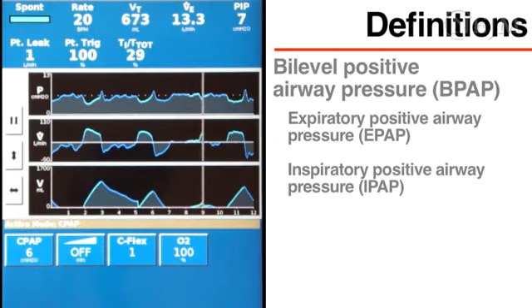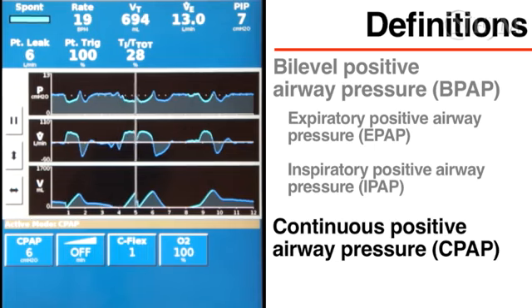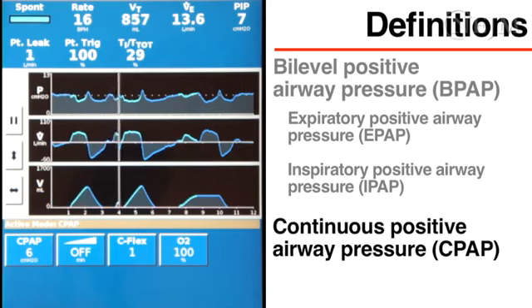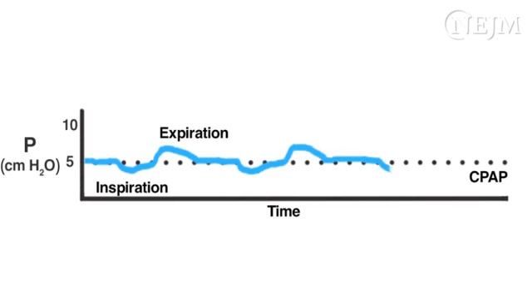Another common non-invasive mode is continuous positive airway pressure, or CPAP. CPAP is a spontaneous breathing mode that is distinct from BPAP. In CPAP, the ventilator delivers one pre-specified positive pressure throughout the respiratory cycle. It does not deliver additional inspiratory pressure, and therefore does not directly support ventilation. This graph shows airway pressure in a patient receiving CPAP. The pressure falls during inspiration as the patient takes spontaneous, unsupported breaths, and returns to the CPAP value during expiration. Many ventilators can also briefly reduce airway pressure during expiration to increase patient comfort.